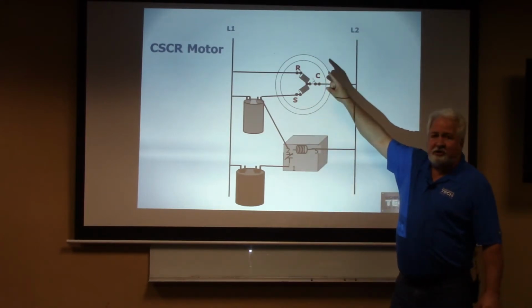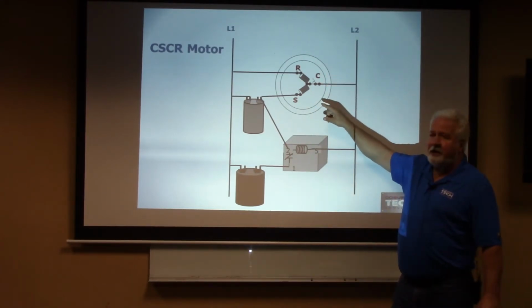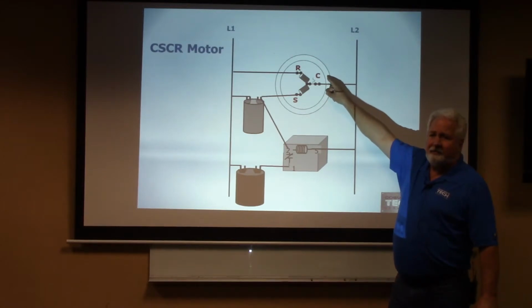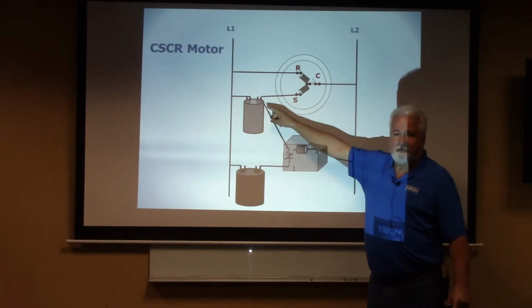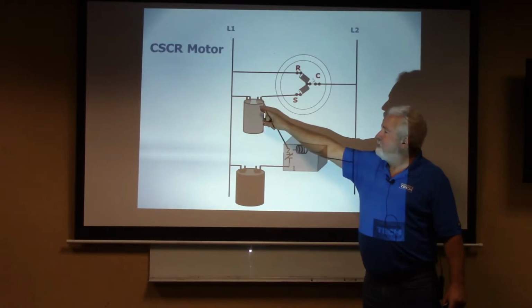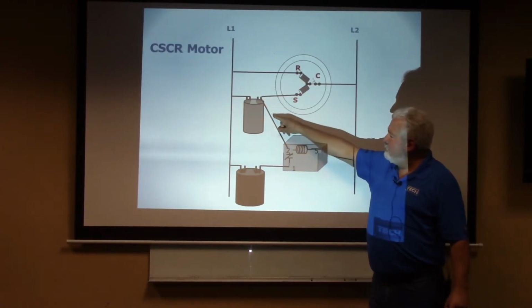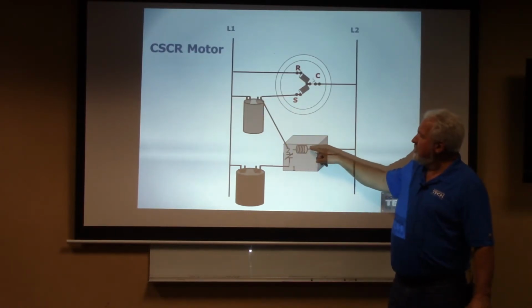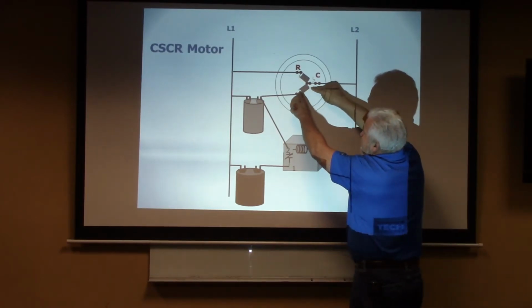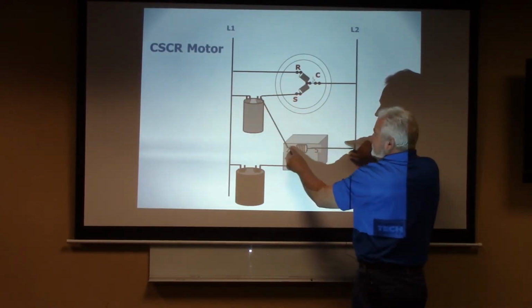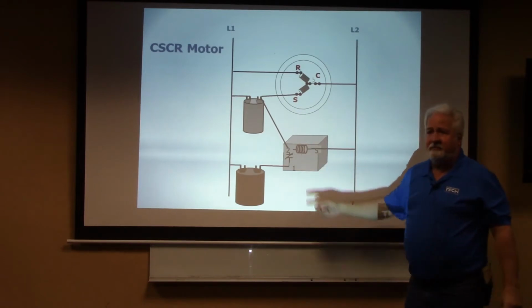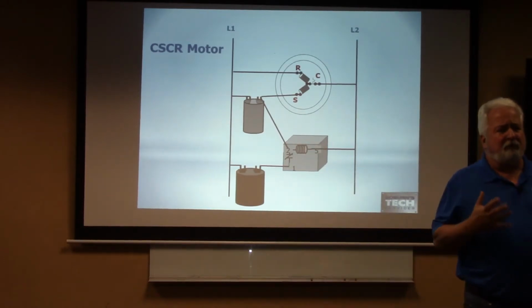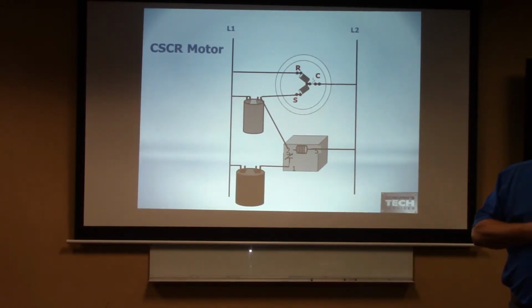When that thing starts running, it starts generating what? Back EMF to that capacitor. Is that right? What's connected to that capacitor? Oh, that coil. So that back EMF is going to that coil. Is that right? If I had a 24 volt contactor and I only put 15 volts to it, would that contactor pull in? It waits till it gets real close to 24 volts.